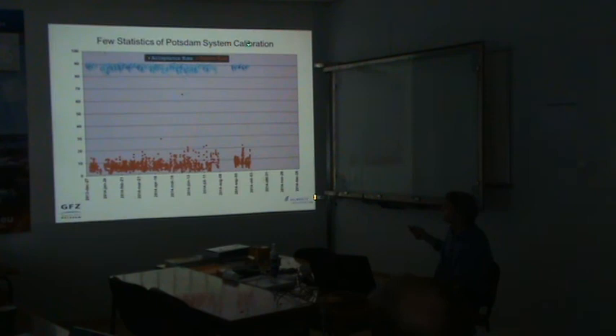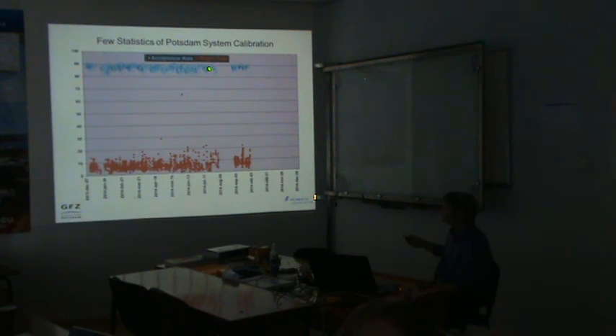A few statistics of the Potsdam system calibration from the end of 2013 up to now. You see the return rate is always kept, shall be kept below 10% or not much more, but sometimes whether the automatic has failed or the observer is lazy and says, oh, I want to go home, why not perform the target run with 65% of return rate? Of course I have to eliminate it. In case I accept this calibration run, I will be assigned a range bias. The acceptance rate is more or less constant, a little bit before 90%.